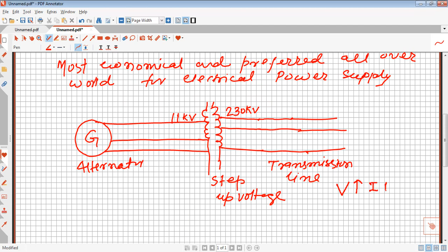The reason behind it is, if we increase the voltage, the value of current will decrease. If the current is decreased, then the losses in the line will also decrease, because loss is I square into R. So if the current is decreased, the loss will decrease very fast, because it is a square of the current. So we are increasing the voltage so that the losses of the transmission decrease.